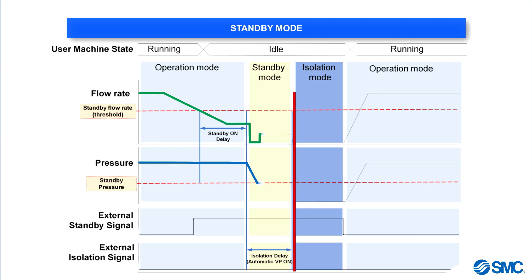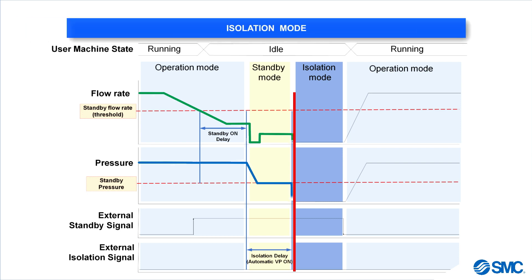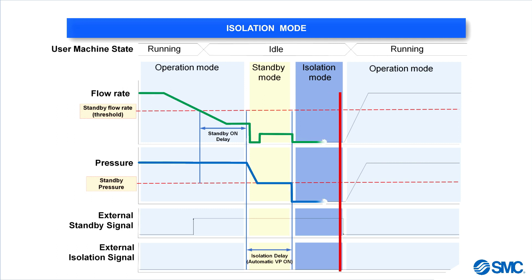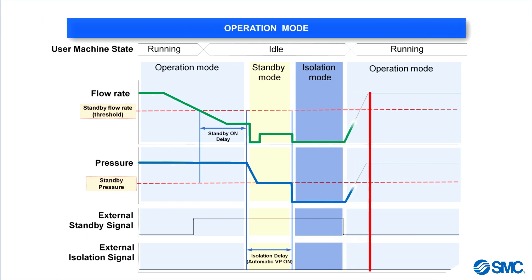Any leaks, open nozzles, or vacuum applications will consume less air due to the reduced pressure. If the system remains in standby mode longer than the isolation delay time period, the system can close the residual pressure relief valve, reducing leaks and air wastage even further. When the standby signal is reset to off, the system goes back to operation mode and increases pressure back to working pressure.